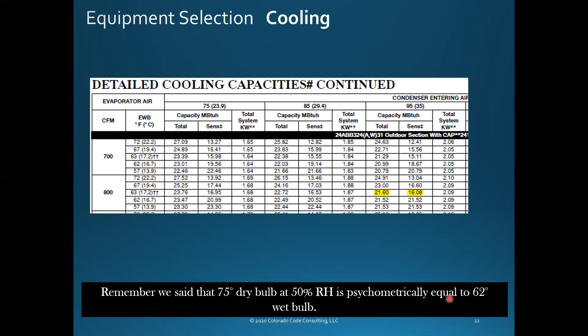75 degrees at 50% relative humidity is psychrometrically equal to about a 62-63 degree wet bulb. They've now started printing things out like this, and I'll show you why. We're going to use this 63 with the little double-T note here to start with. So right or wrong, good or bad, AHRI and everybody else decided that comfort is 75 degrees at 50% relative humidity for inside summer design. So that's what we're designing to.